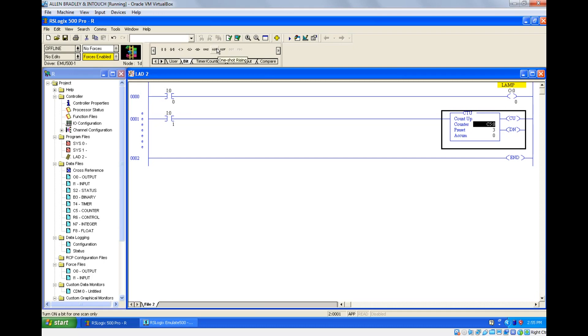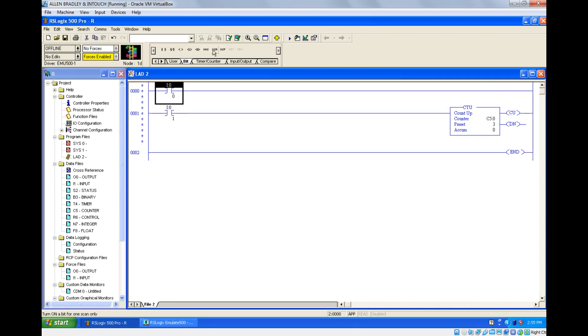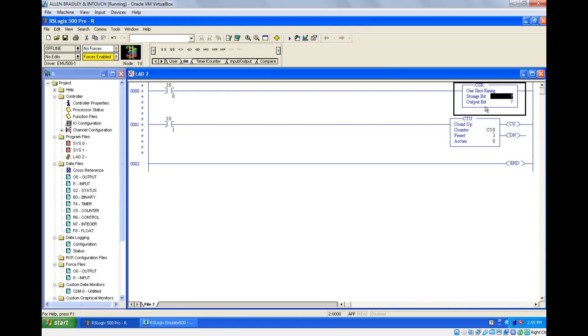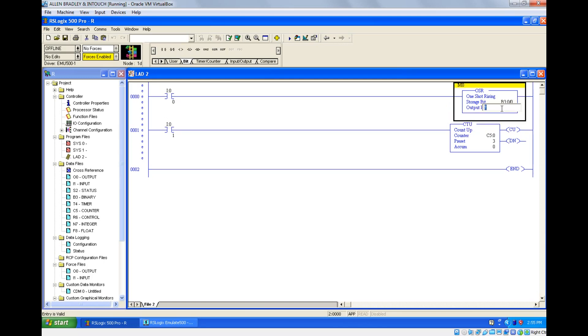So what is one shot rising? The name itself tells you — one shot rising fires whenever the input changes from 0 to 1, which is the rising edge. Whenever the input changes from 0 to 1, it will give one pulse. One shot rising is an output instruction — it goes on the output side. The block asks for two question marks: one is the storage bit and another is the output bit. I'll give b3:0/1 as the memory address for both.